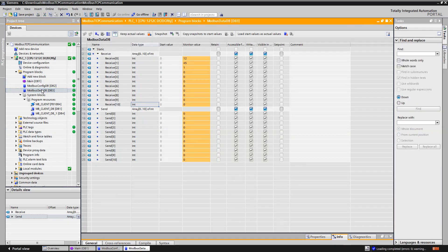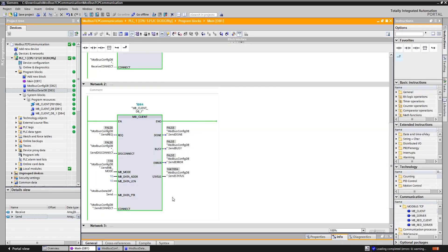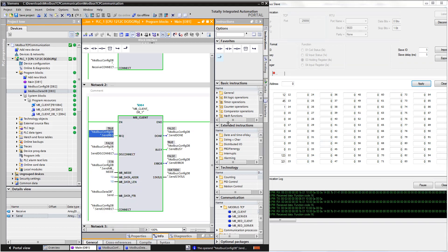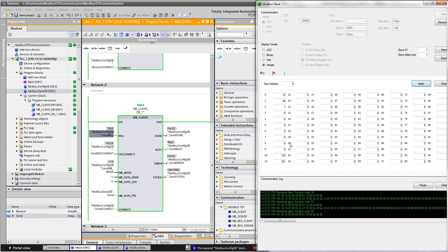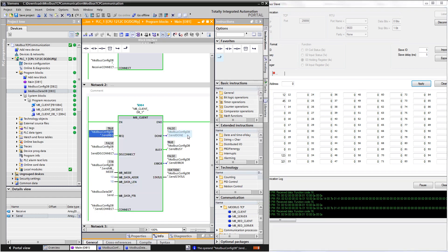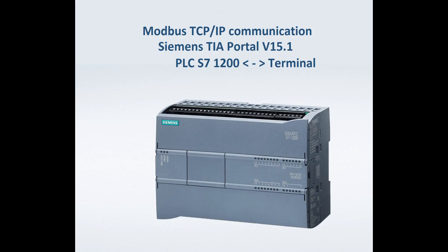Now just add some numbers to the sending DB and they will be received by the slave client. If it's not working, check the status number — but this number is being overwritten, so it's a good idea to save its value when the error bit is on. Sometimes you have to restart the PLC to make the function work. Some devices require disconnecting after every transfer — refer to your device manual. Also be careful when editing DBs while online: there are two values — one is the starting value, which is loaded when the PLC starts, and the other is the monitored value, which is in the PLC right now. Always change both. Also check the firewall if it's blocking the Modbus traffic.